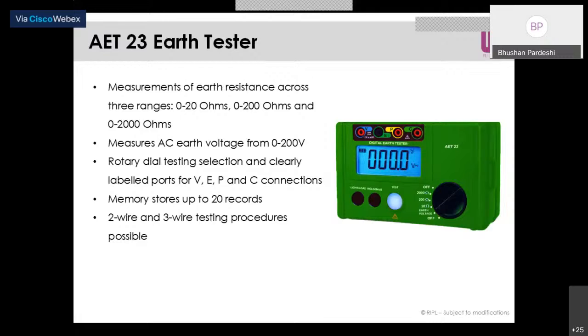But you will be thinking that earth resistance can be measured within 10 ohms or even 5 ohms only. So why have we provided the two extra ranges, 0 to 200 ohm and 0 to 2000 ohm? Apart from measuring the earth resistance, you can also measure other resistance. If you want to measure other low resistance values, then you can measure above 20 ohm, up to 2000 ohm, that is 2 kilo ohm.